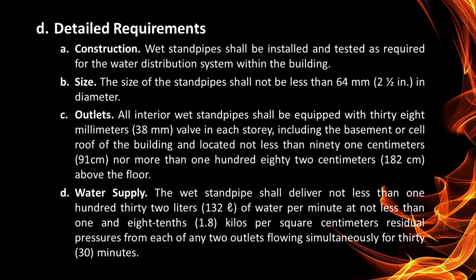So, detailed requirements. Construction. Wet standpipe shall be installed and tested as required for the water distribution system within the building. Size. The size of the standpipe shall not be less than 64 mm in diameter. Outlets. All interior wet standpipes shall be equipped with a 38 mm valve in each story, including the basement or cellar and the roof of the building, and located not less than 91 cm nor more than 182 cm above the floor. Water supply. The wet standpipe shall deliver not less than 132 liters of water per minute at not less than 1.8 kilos per square centimeter residual pressure from each of any two outlets flowing simultaneously for 30 minutes.